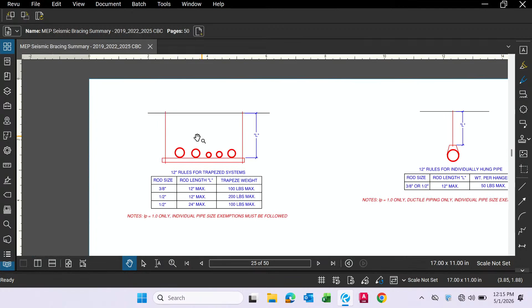For example, based on this new code cycle, the 12-inch rule for a trapeze system: if the rod is 3/8 inch and it's no longer than 12 inches, and the trapeze is 100 pounds or less, it can be exempted. If the rod is 1/2 inch, the weight goes up to 200 pounds, and if the length goes up to 24 inches, that weight comes down to 100 pounds. But notice that this only applies when the importance factor is 1.0 only, and you have to maintain the pipe size exemption previously. In other words, if any of these pipes require bracing per the previous requirements, then you can't apply the 12-inch rule. So again, this only applies to an importance factor of 1.0. If any of these pipes has an importance factor of 1.5, this 12-inch rule doesn't apply.